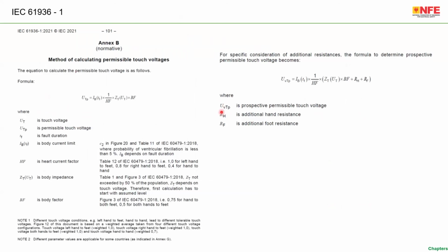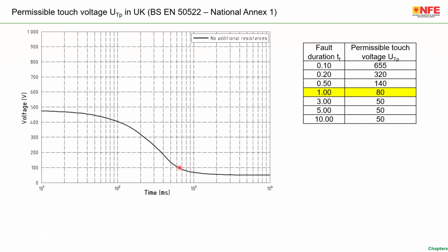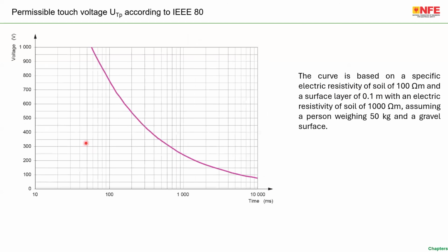Now the standard gives the annexure which can be used to calculate a figure. If you want, you can calculate such figures. But anyhow, the IEC figure stands good for applications like India. On the other side, IEEE 80 gives a different figure. As you can see here, the prospective touch voltage with respect to time. Now there is no upper limit if the disconnection is happening within 100, you see 30, 40, 50 millisecond, then there is no upper limit, whereas the IEC makes a certain upper limit. And this curve is also based on a different assumption, or an assumption which is a little bit different from what is explained in the IEC standard.